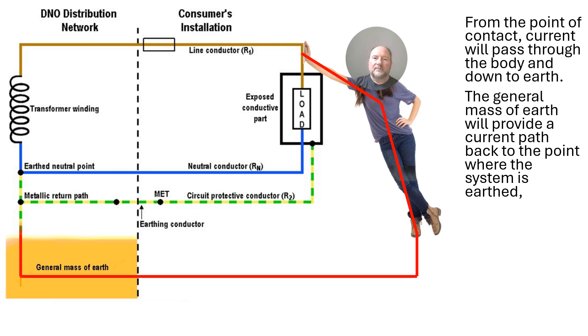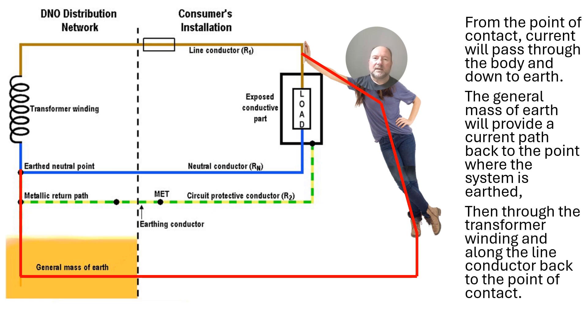And it will find its way through the general mass of Earth and find its way eventually back to that Earth neutral point of the transformer secondary winding in the DNO substation. The current will then pass through the secondary winding and down the line conductor back to the point of contact. So that is the whole path that the current will take.